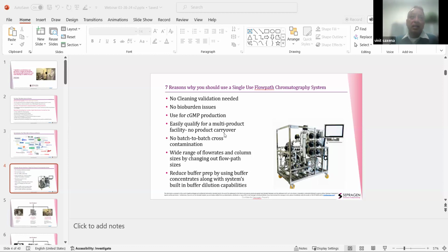So we've got a 20-liter per hour system, 100-liter per hour system, 600-liter per hour system, 1,000 liters per hour, 3,600 liters per hour. All of these are single-use flow path systems with disposable sensors, pump heads, flow paths come sterile, etc. They have smart GMP 21 CFR Part 11 compliant software. The materials used are USP Class VI, ADI-free materials, and the flow paths are fully integrated and can be installed in about 15 minutes. You've got your standard sensors of pH, conductivity, UV, flow, pressure, air, etc.